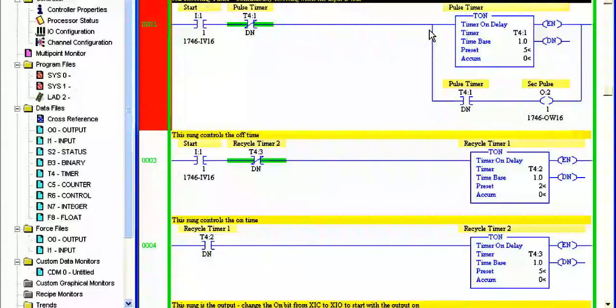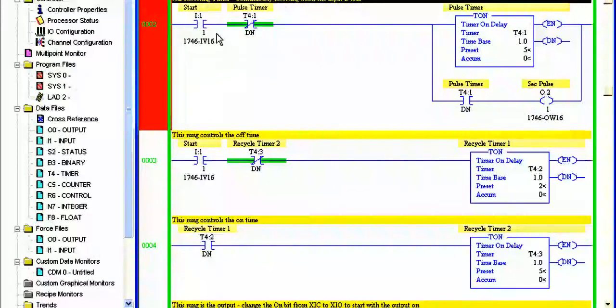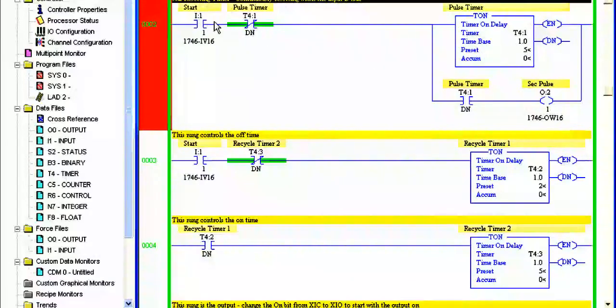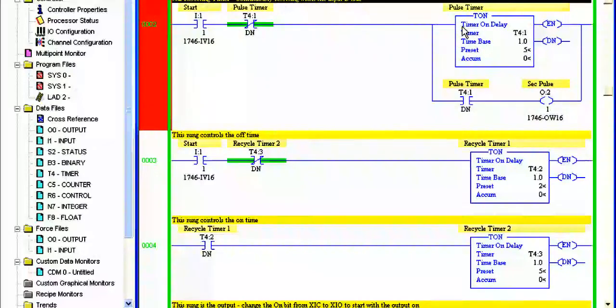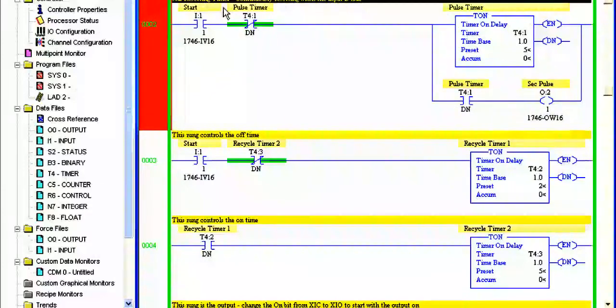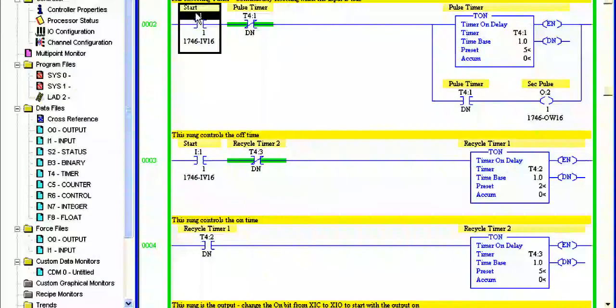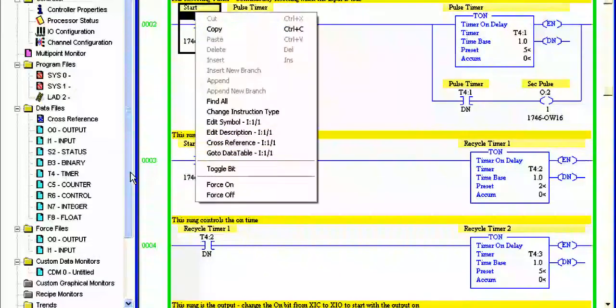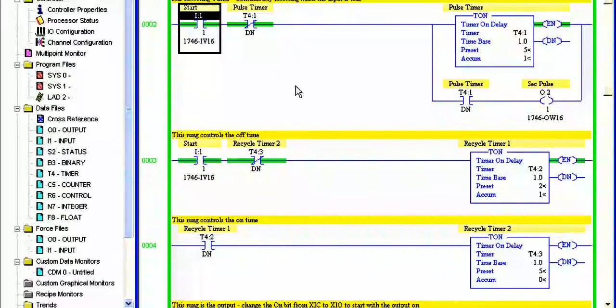And the Allen Bradley SLC doesn't have an easily configurable clock pulse within it as some other PLCs have. So this may be the answer to easily configure that. With this one it's a simple start input and it's got a closed bit of its done bit. So if I turn the start bit on the timer starts timing. And I've got a little done bit here to pulse its output. This is not absolutely necessary in your circuit, I've just put it there to demonstrate it. But you can use the done bit of that timer anywhere in your circuit to perform a regular pulsing.